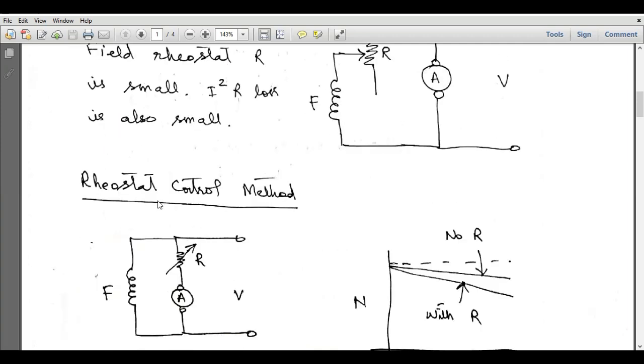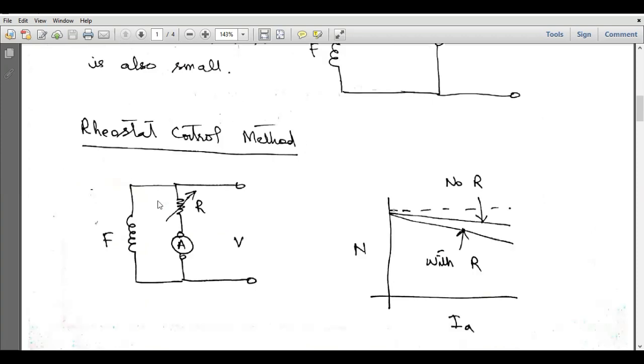The rheostat control method is another method. Here we use a variable resistor in series with the armature winding. When we increase this resistance, the voltage drop across the armature — the Ia·Ra drop — will increase, and as a result the speed will decrease. So when we increase this resistance, Ia·Ra increases and speed decreases.